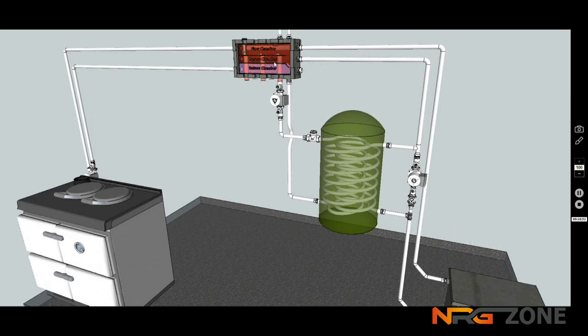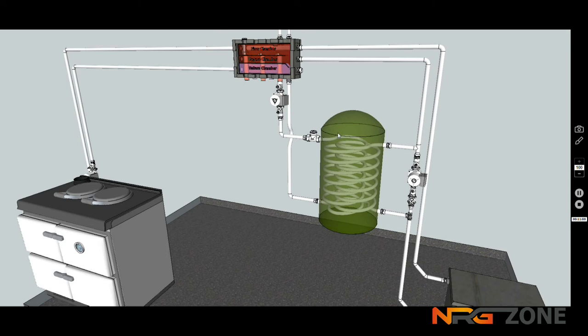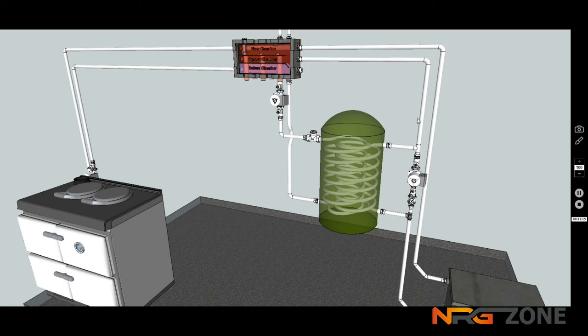Whether you use an energy zone or not, it's always a good idea. The connection point to a cylinder should be a non-return valve. The reason being, if heat is introduced in, it won't drift back out, and lose its heat contents in the pipework. The pipework will act as a radiator. So, it just keeps the hot water hotter much, much longer when you prevent it coming out. Of course, you can't use a non-return valve on a primary circuit.